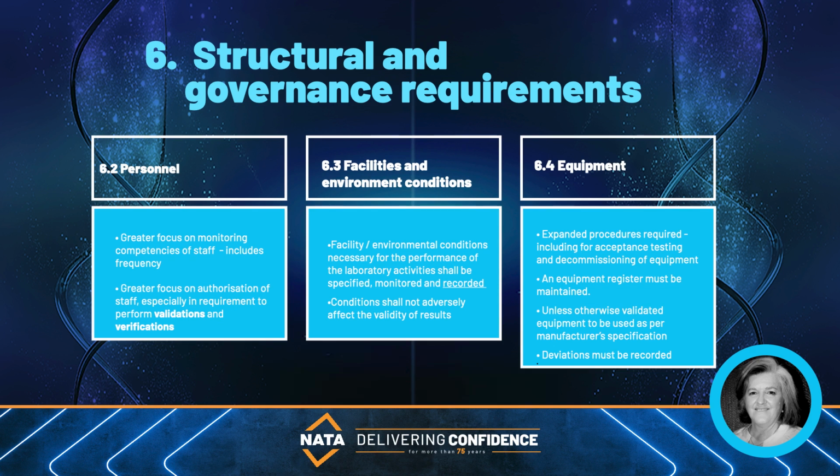Labs shall have preventative maintenance programs based on the manufacturer's instructions, and any deviations from schedules or instructions shall be recorded. Records for each equipment item that influences results shall be maintained and be available for at least the lifespan of the equipment, potentially longer.